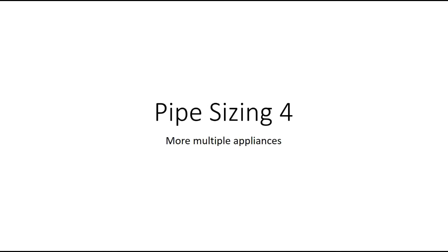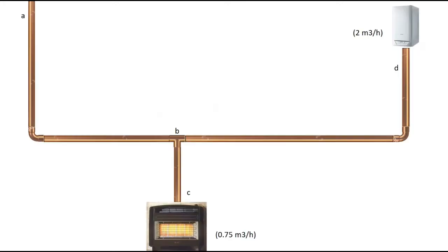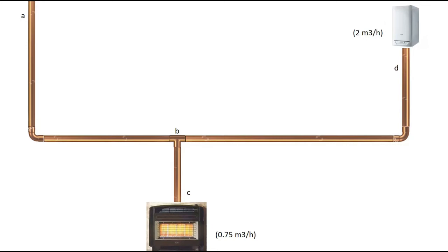Pipe sizing for multiple appliances. Here we have our system — it's got a gas fire and a boiler. We've already gone through the first section between A and B, and now we're going to look at the section between B and C. If we remove it, we can see that the only appliance that's going to be affected is the fire, so that's the only appliance we need to size.